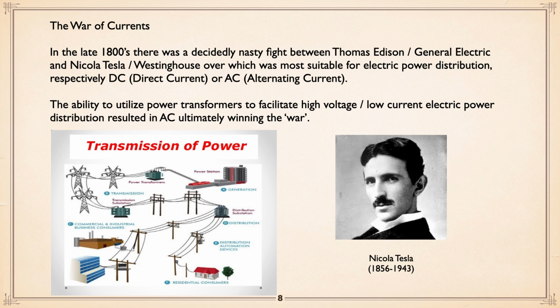The ability to utilize power transformers to facilitate high voltage, low current power distribution resulted in AC ultimately winning the war. With DC, they were talking about every few blocks you would have a generating site, which is just totally impractical in the long run. So if we look at the system here, transmission of power, generated at a power station, be it thermal or hydroelectric, power transformers jack that up high, into the hundreds of thousands of volts in a lot of cases, so you can go super long distances. Then when you close in on a city, the voltage is reduced by transformer, and then distributed, and then reduced yet again to go out to various businesses where it is reduced down to what you want.